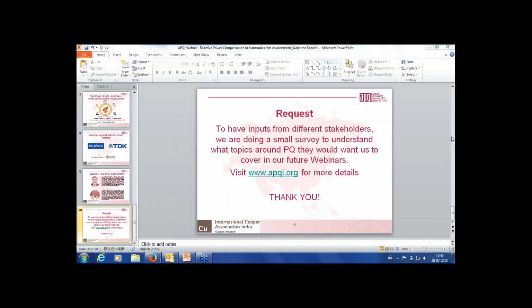Okay, sir. Thank you. There is another consequential question. The question basically he is asking for the opinion. By improving the neutral earthing of transformer, will it help to reduce the third harmonics level? Let me answer this. Basically, by improving the neutral earthing of the transformer, it won't help reducing the third harmonics level. But the consequence of high third harmonics can be addressed by improving the neutral sizing, as Dr. Rajamani just explained.